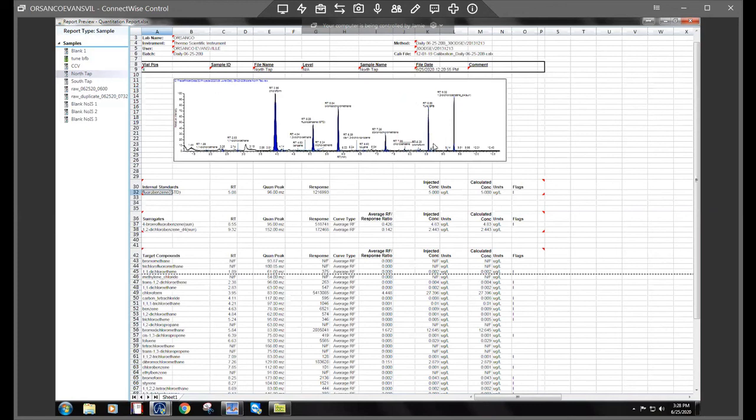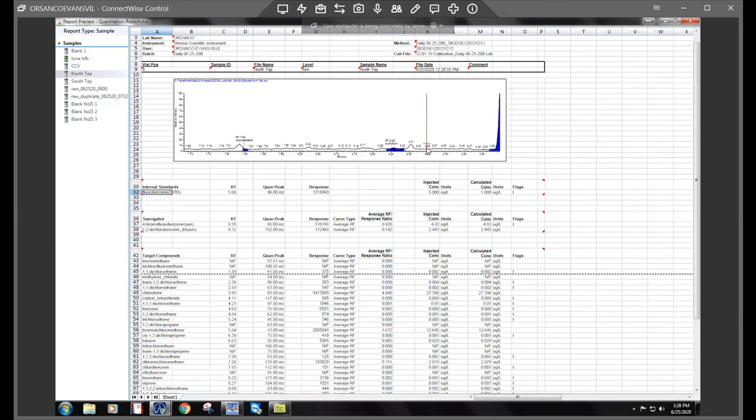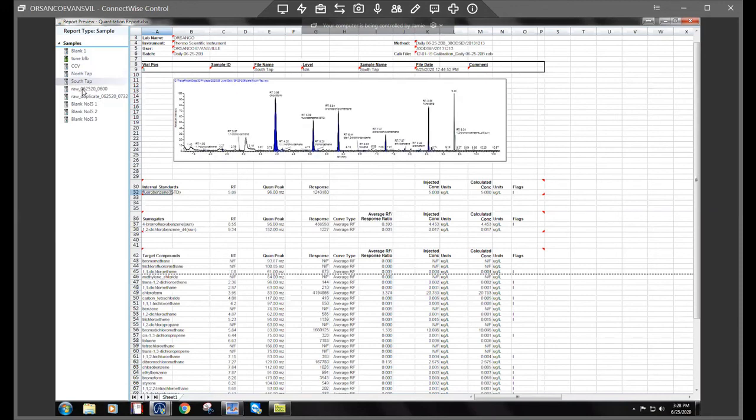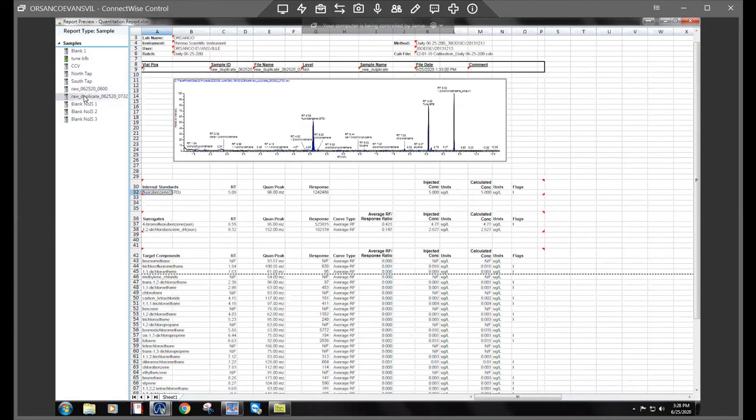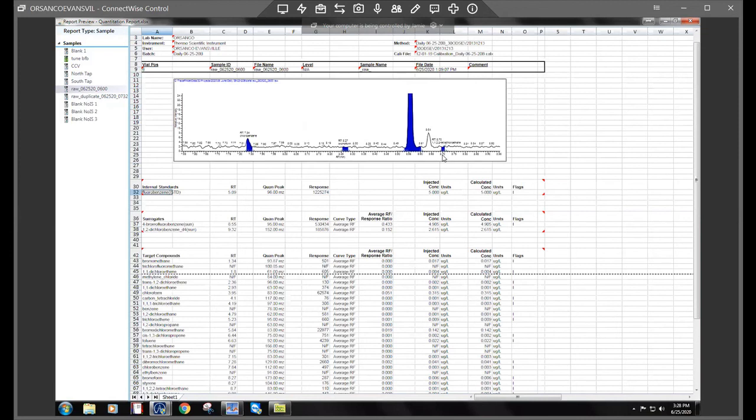And that methanol might help clean out whatever gunk has accumulated over time. And especially if trimming your column didn't do anything, but so that's kind of a few solutions for that. But I would definitely say these are definitely within the instrument versus in the samples.